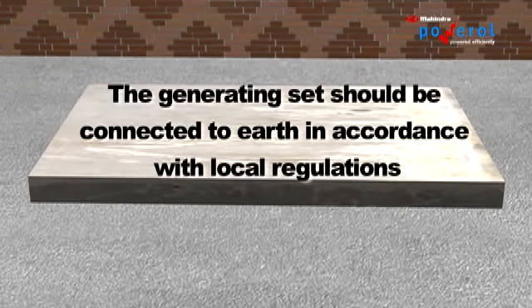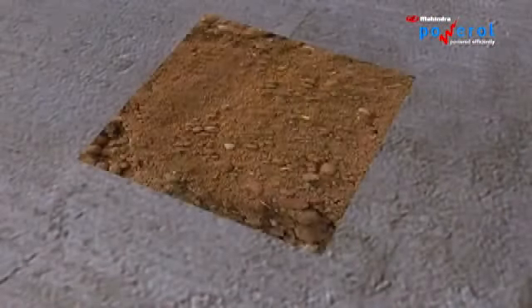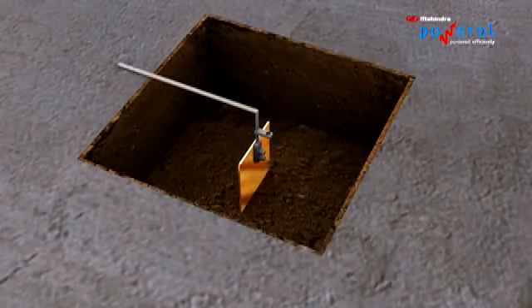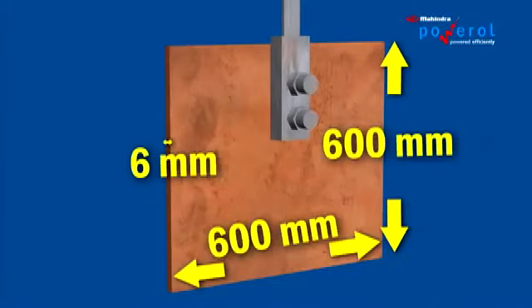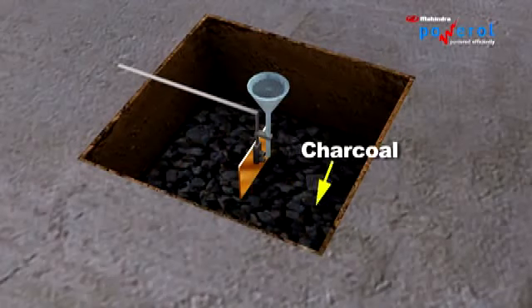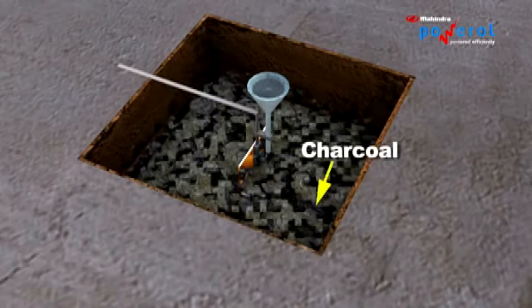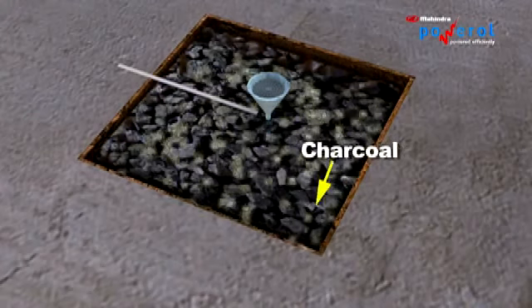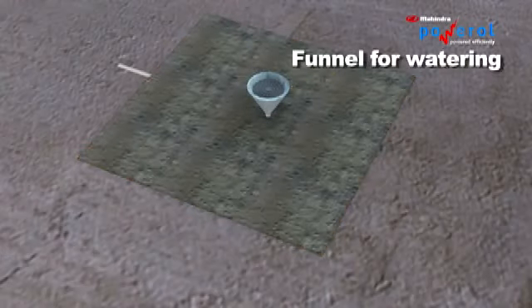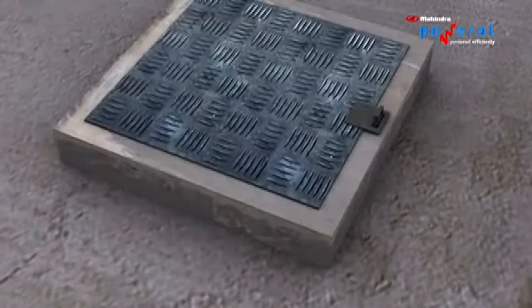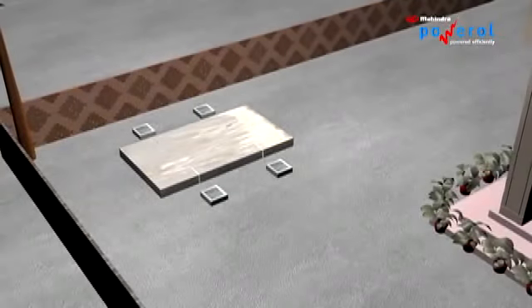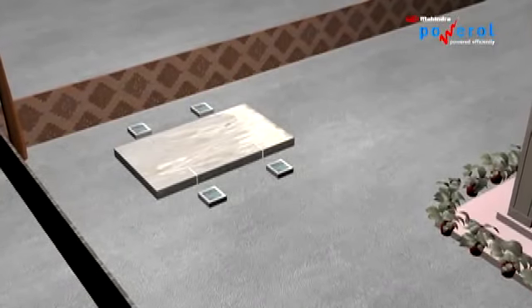The generating set should be connected to earth in accordance with local regulations. 4 earth pits are required as per the Indian Electricity Rules. The neutral earth pits and body earth pits should be located on opposite sides of the canopy.